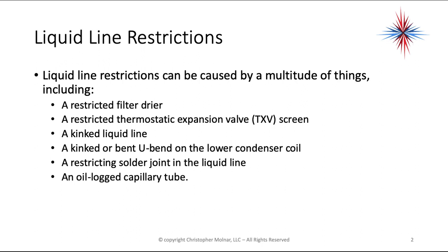All of these can cause restrictions to refrigerant flow. For a restricted filter line dryer, we've already talked about this: put a temperature probe on each side of the filter dryer, and if you have a temperature difference, it's restricted.